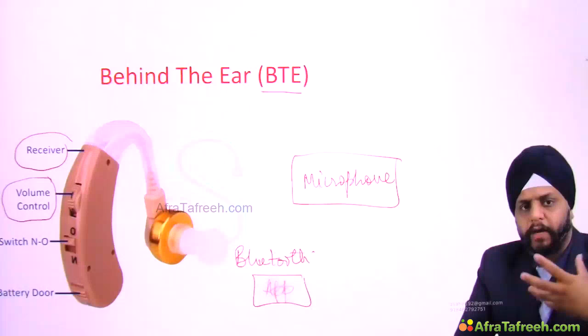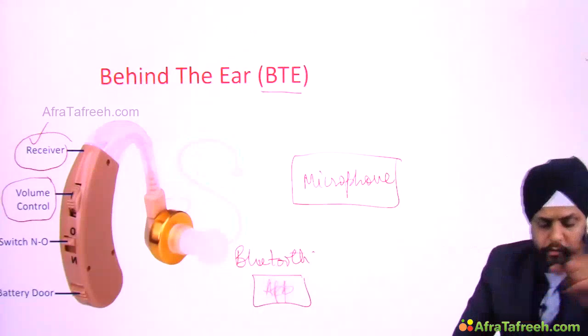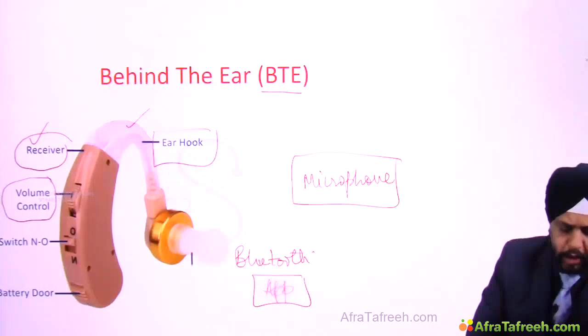So what is the function of this receiver? It converts back the electrical signals which have been amplified by the amplifier into sound signals. The receiver is not receiving the sound, it is converting the sounds which have been amplified. That's an electrical stimulus right now, so that electrical signal is converted back into sound. It gives it to a tube. You see over here, there is a tube connected in a hook shape, coming inside this plastic capping, and it reaches over here, and from there this ear plug is placed inside the EAC, and this hollow tube will bring the sound into the EAC, right?